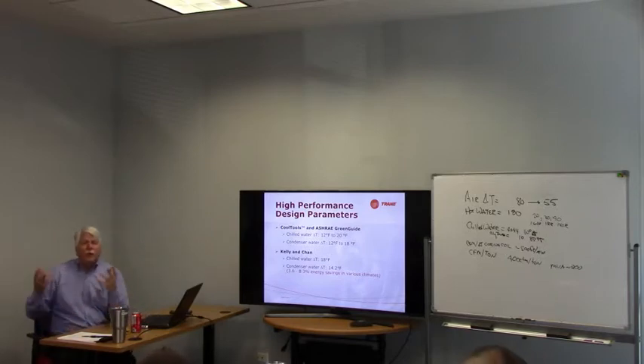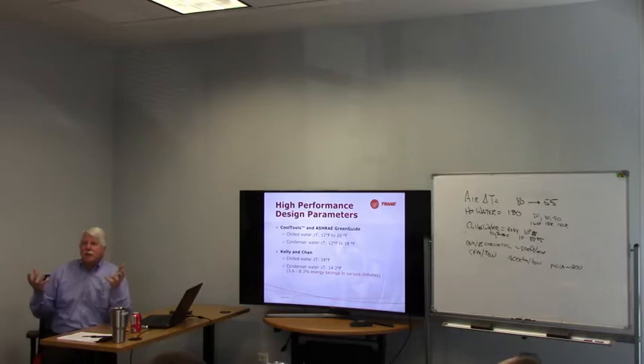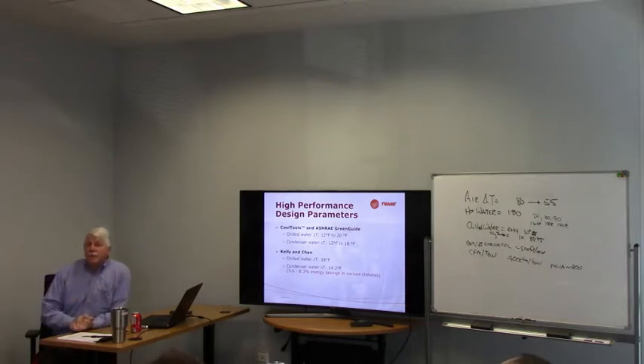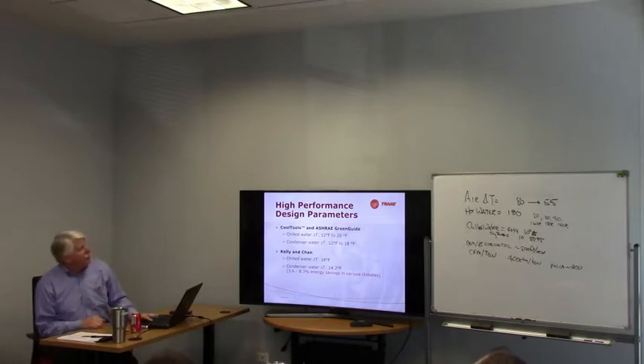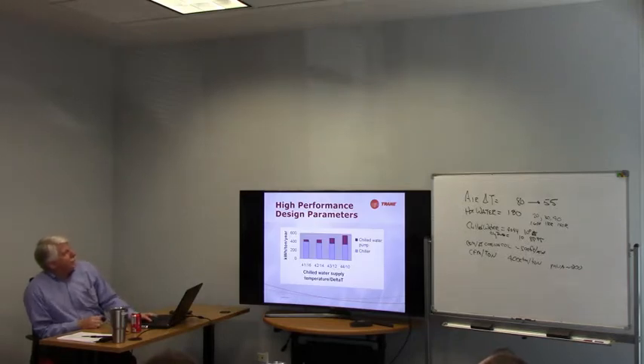Now, when we reduce our flow through the chiller, what energy savings do we get? Where does the energy savings come from? Heat transfer? No, not heat. Pump energy. Right, when we lower the flow, the pump energy goes way down, okay? So we're saving pump energy here.